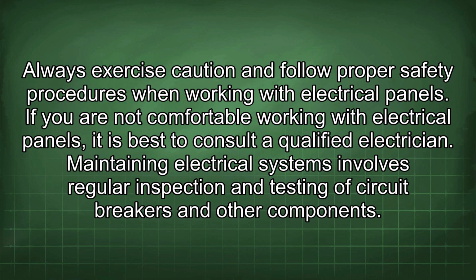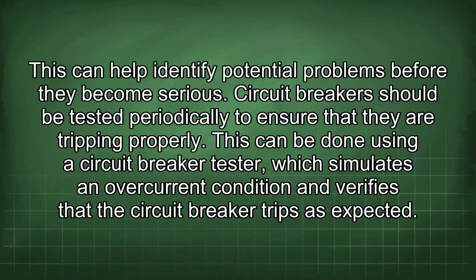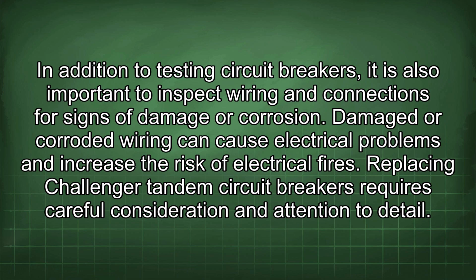Maintaining electrical systems involves regular inspection and testing of circuit breakers and other components. This can help identify potential problems before they become serious. Circuit breakers should be tested periodically to ensure that they are tripping properly. This can be done using a circuit breaker tester, which simulates an overcurrent condition and verifies that the circuit breaker trips as expected. In addition to testing circuit breakers, it is also important to inspect wiring and connections for signs of damage or corrosion. Damaged or corroded wiring can cause electrical problems and increase the risk of electrical fires. Replacing Challenger tandem circuit breakers requires careful consideration and attention to detail.